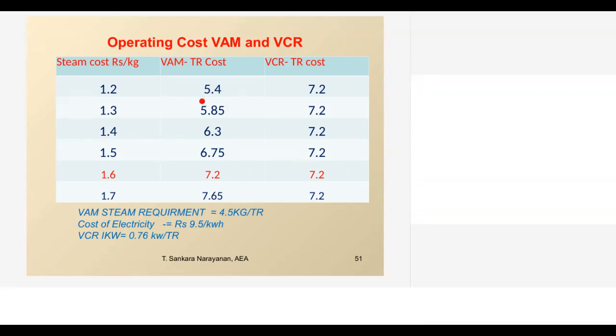The same thing is worked out for vapor absorption and vapor compression systems. A VAM requires around 4.5 kg of steam per TR for a 2-stage vapor absorption machine. For the VCR, the compressor input is 0.76 kilowatt per TR. Based on that, when the steam cost changes, the operating cost of the VAM also has to be reviewed. Up to 1.5 rupees per kg of steam, it is all a fine advantage. The moment steam cost goes to 1.6, both VAM and VCR, primary fuel cost is almost equal. Along with this, you have to add auxiliary costs. Whenever you put in a vapor absorption machine, your cooling tower load will be doubled. So we have to review this type of cost.